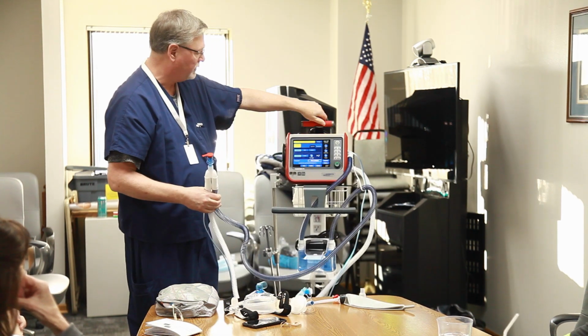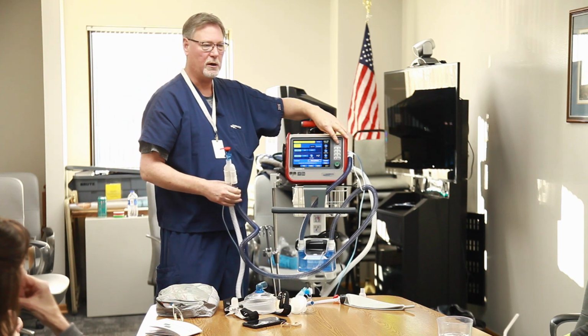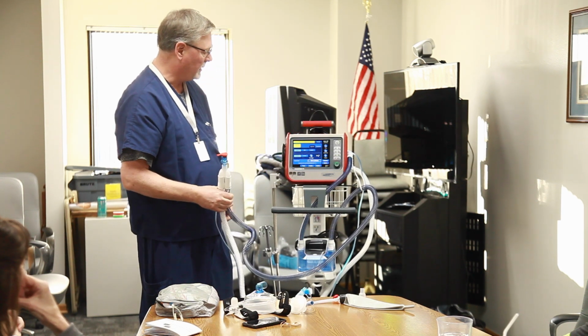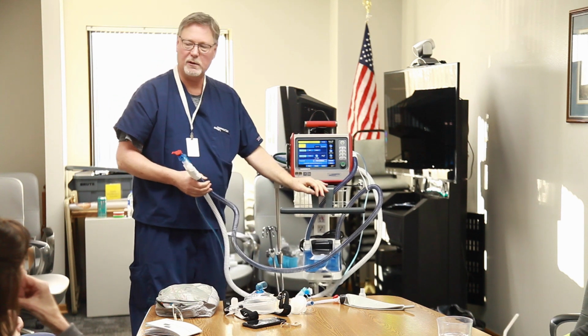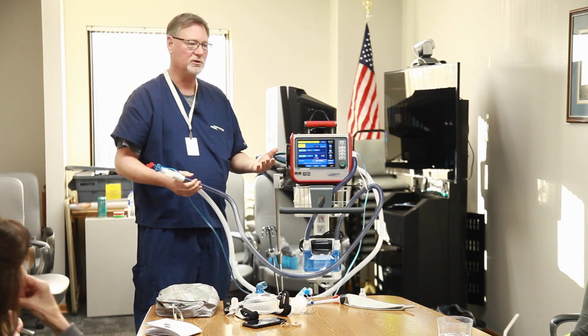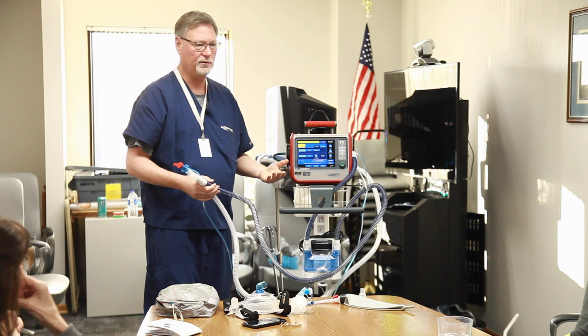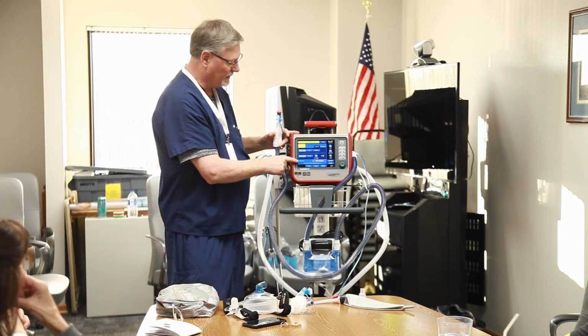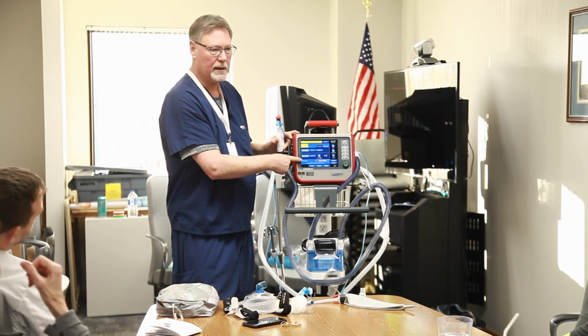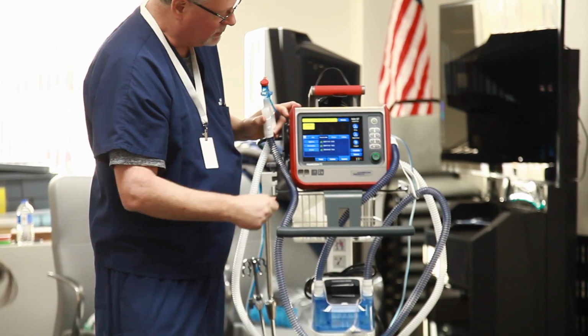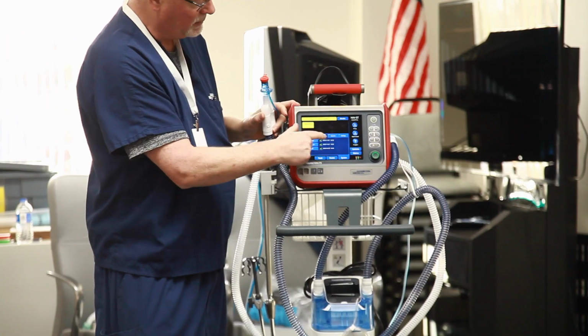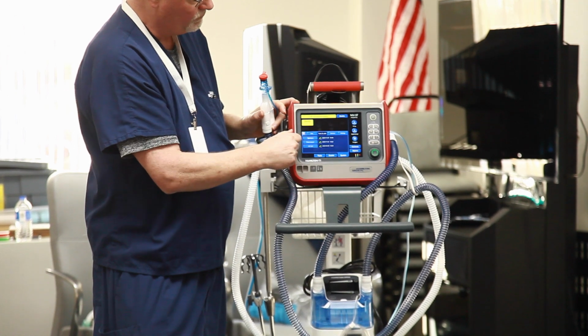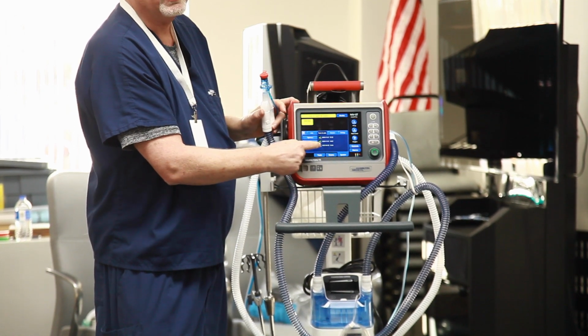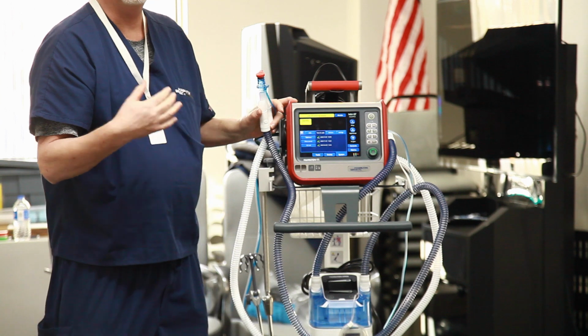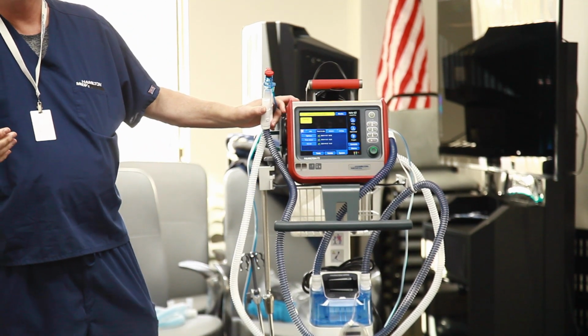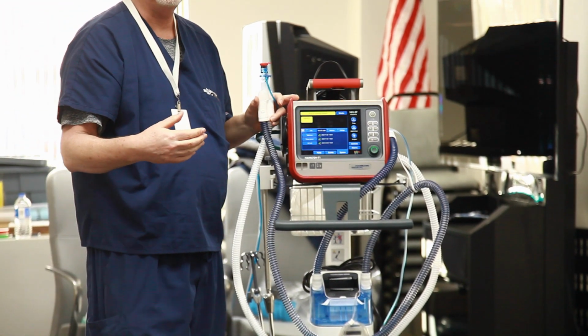I powered up the ventilator with my power button, so now this is the way it's going to come up. Anytime we put a new circuit on, we need to do a pre-check. We have to make sure it's tight. We have to calibrate the flow sensor. To do that, we have a little pre-check button right here, pre-op check. Push it. It opens up the systems tab to the tests and calibrations. O2 cell, as long as there's a green check mark there, you're good to go. Don't calibrate that every time. Only calibrate it when it tells you to.